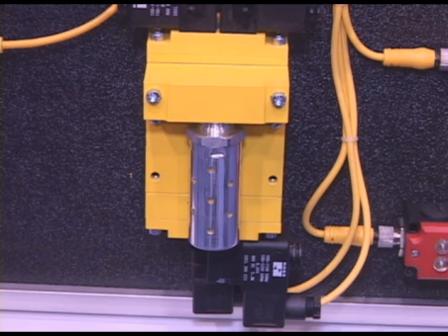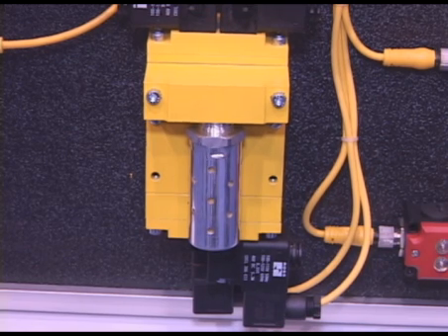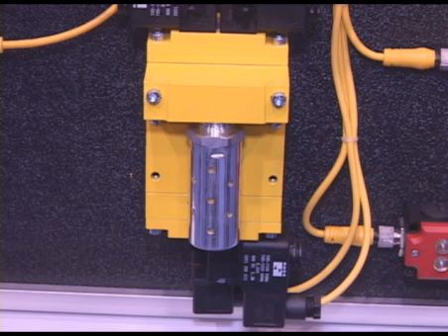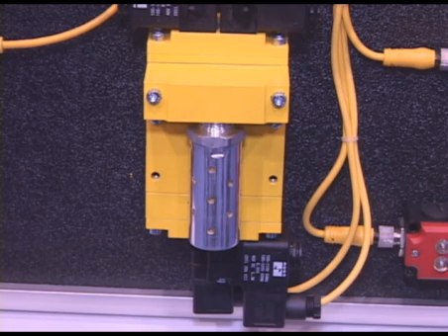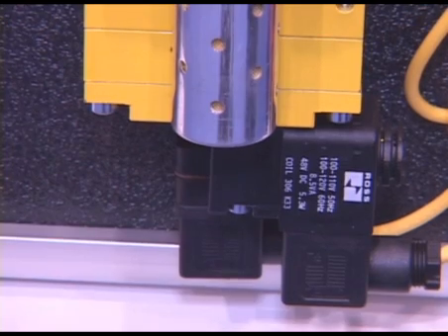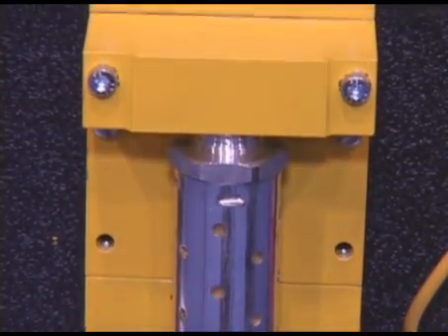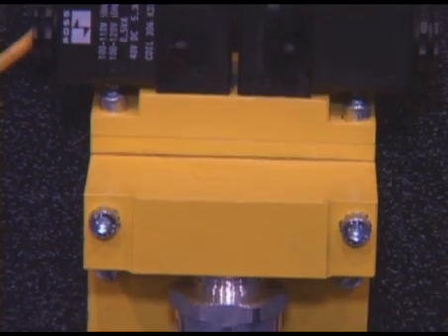This is the Ross DM2E valve. It's a control reliable pneumatic dump valve to be integrated with your safety systems for machine guarding applications. Similar to safety devices used for your electrical controls and safety relays, it's redundant, it's monitored, it fails to a safe condition to provide safe pneumatic control for your packaging equipment.